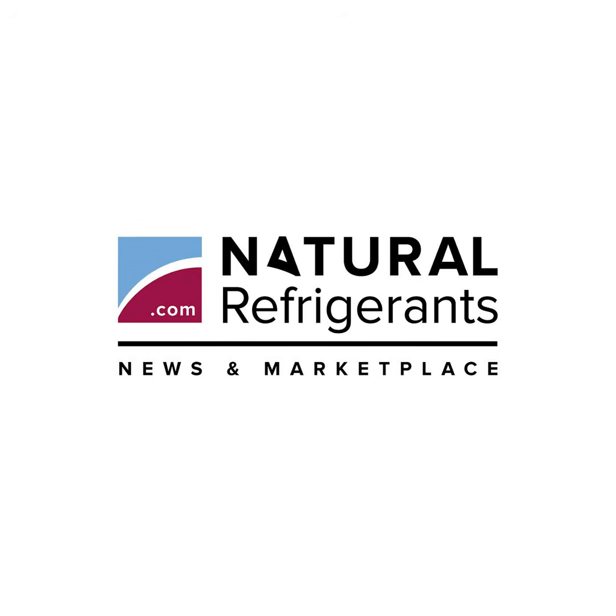Technology uptake. We are starting to see sales for R290 chillers in Latin America, Yanez said, who noted that end users in the region are willing to try new technologies as they work to comply with the phase out of HFCs mandated by the Kigali Amendment. In LATAM, self-contained refrigerators commonly use hydrocarbon refrigerants, while large industrial plants rely on ammonia or CO2. However, HFCs still dominate medium-sized commercial and industrial systems. FB Industrial's R290 chiller fills this gap, particularly in MT applications, Yanez said.